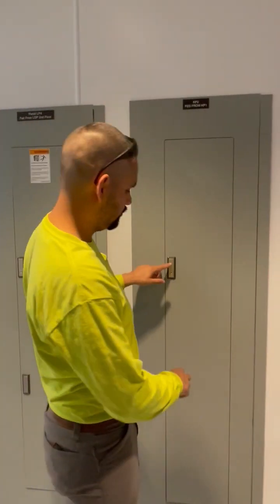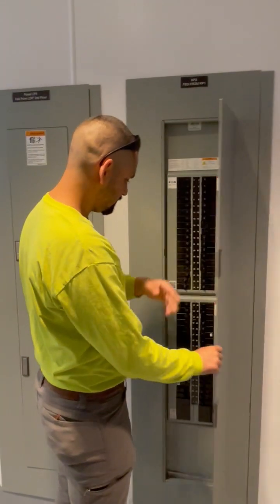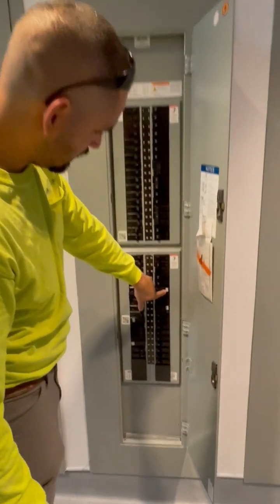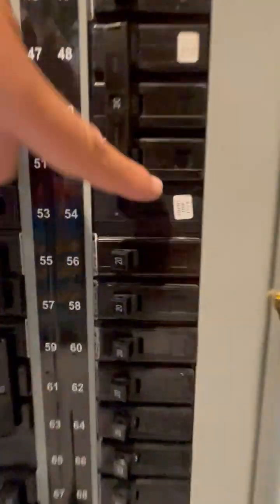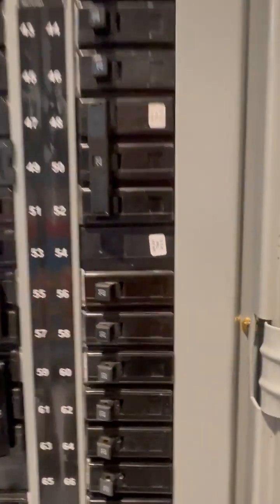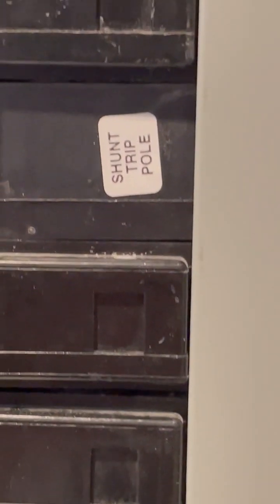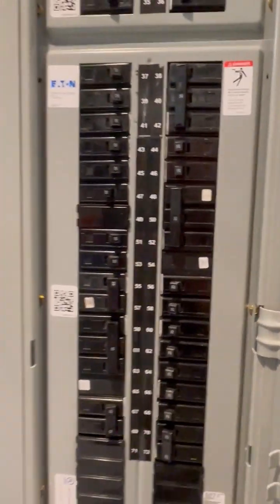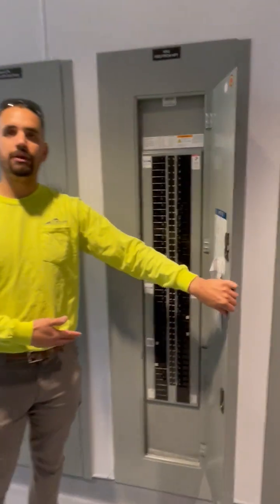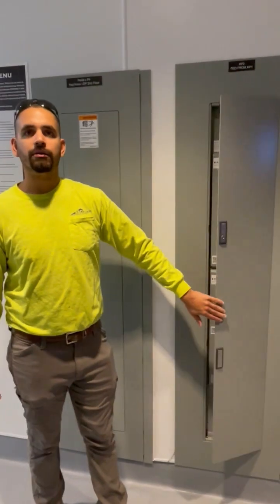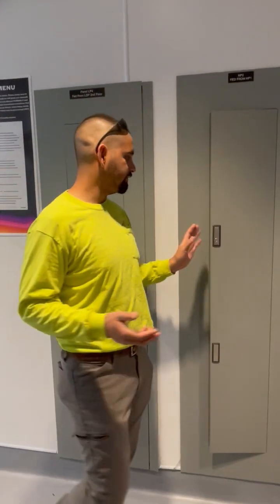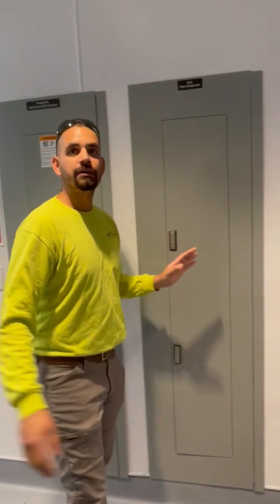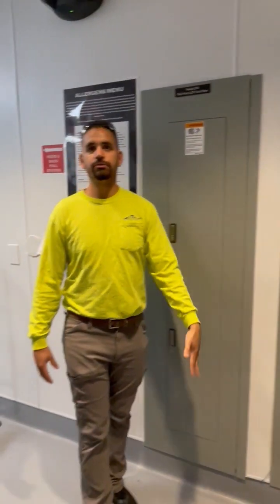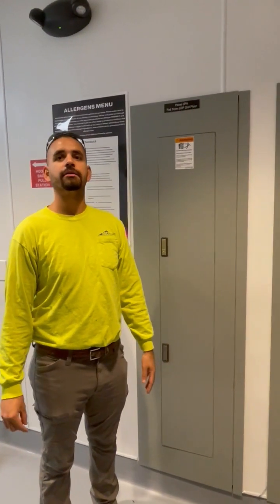In here we have your shunt trip breakers. You can see some of them are labeled shunt trips. Those are the ones that trip in case of a fire alarm. Cool. So when there's a fire, those will be tripped. Those will have to be reset manually. So when a fire alarm goes off, all the shunt trip breakers immediately flip, and then you need to manually turn them back on.